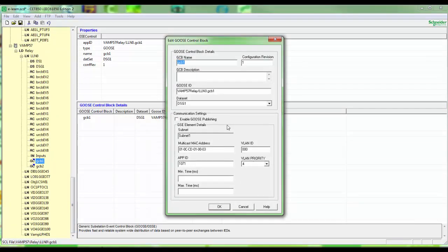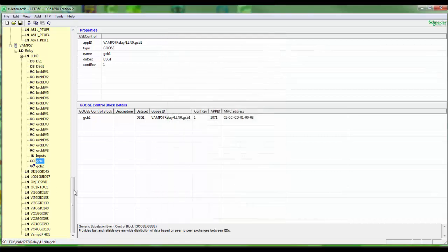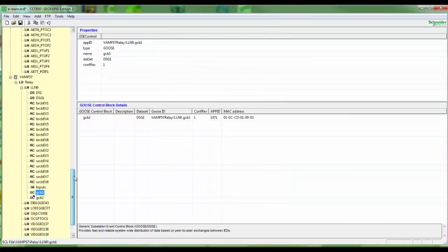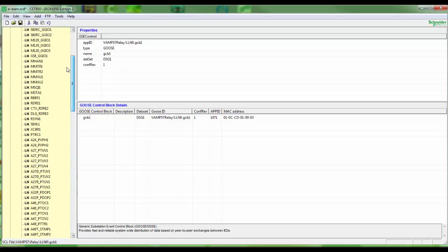Parameter GOOSE publishing has to be set manually in the GOOSE control block of the inserted IED. GOOSE minimum and maximum cycle time has also to be set in case the fields are empty.